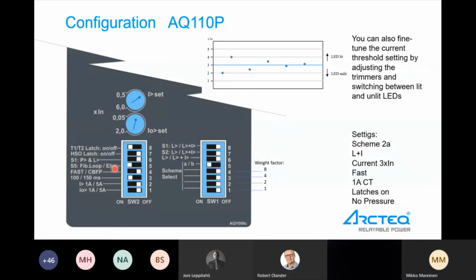Fiber loop or this AQD, we can have it fiber loop here. We don't have AQD here. Fast or CBFP: in our example, we have only fast. So let's select this one to the left. And because it's fast, this doesn't actually matter. It can be set off here. And then currents, 1 amp CTs from here. So this is quickly switch 1 and switch 2. First the scheme, then light plus current, 1 amp CT, fast activation, fiber loop, no pressure, and the latch is on.